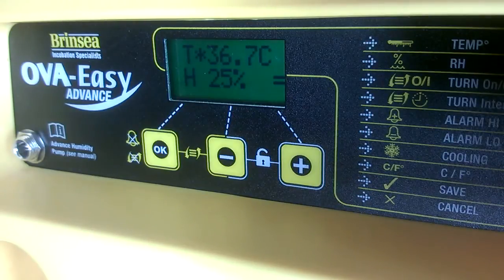So there you go. You can now see that the temperature in the menu is at 36.6, rising to 36.7, and it will continue to rise now to hit its target temperature, which is still 37.5. It's just that we have now told the machine that instead of 37.5, it is actually 36.5 in the machine, because that is what the thermometer is measuring. And our machine is now going to work to bring the temperature back up to 37.5, which is where we want it to be.